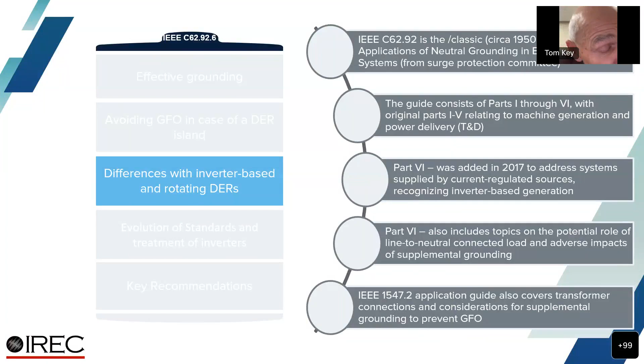As I mentioned earlier, we've tried to get the standards to sort of catch up with inverters, because most of the standards originally have been written for synchronous machines. So there's a classic one, from the 1950s, grounding of utility systems really was basically for synchronous machines, C62.92, and so more recently, as we had a lot more inverter connections, we've updated the C62.92 to treat the inverter-based connections differently.